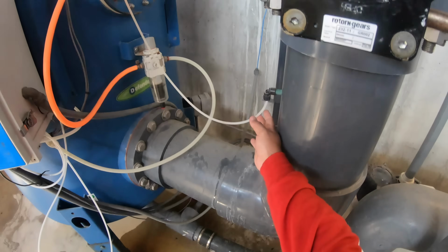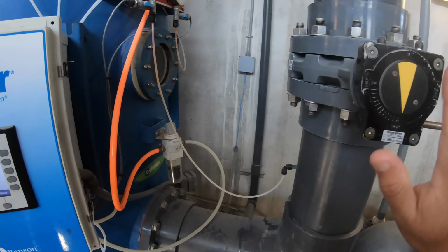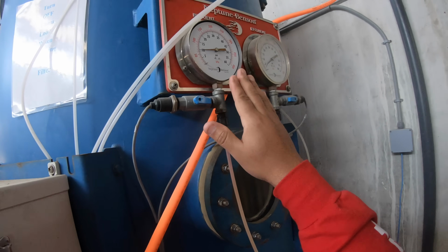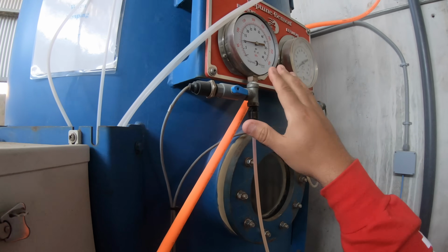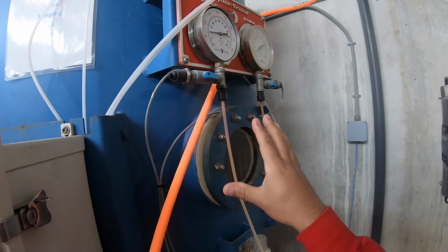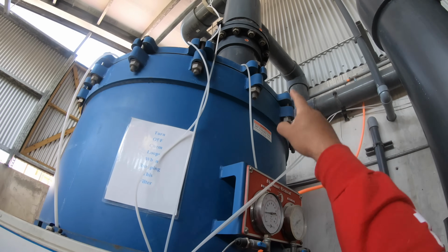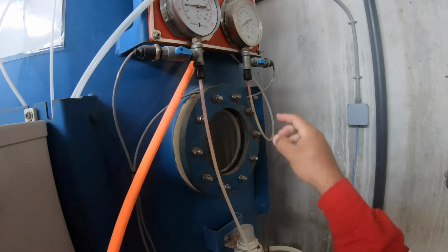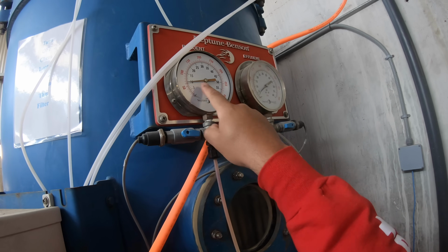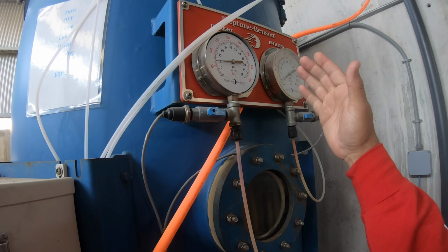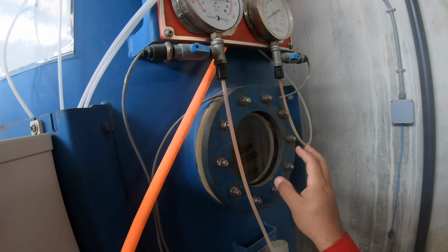So if you follow right here, this tube is coming directly from the pump. See it? Coming from the pump. This is influent, and the easy way to figure that out, what's the difference between influent and effluent? Influent is in pressure, okay? Effluent's out pressure. So what it's saying is currently the pressure in the filter at this point is 10. This one goes from the top, and that's the out pressure, okay? So what it's saying is my differential right now is roughly 10 minus 2, so roughly 8 differential, 8 PSI. The maximum you can do here is 15 on this filter specifically, okay?